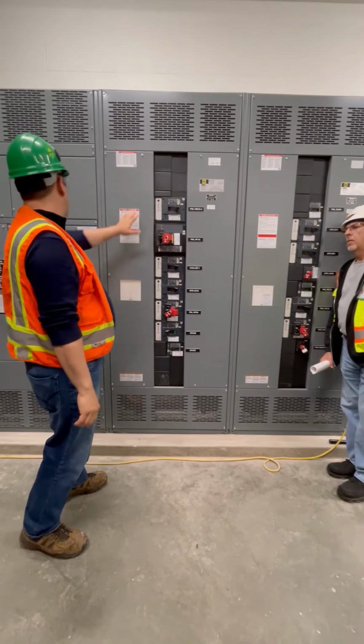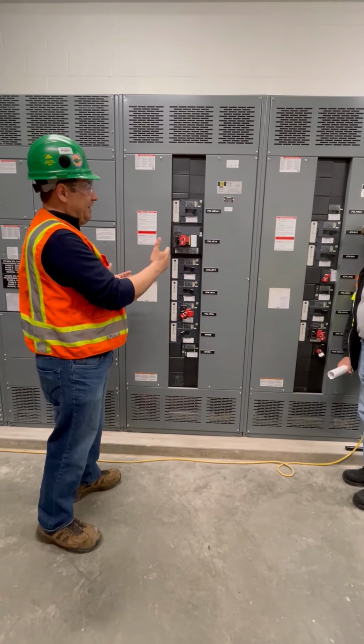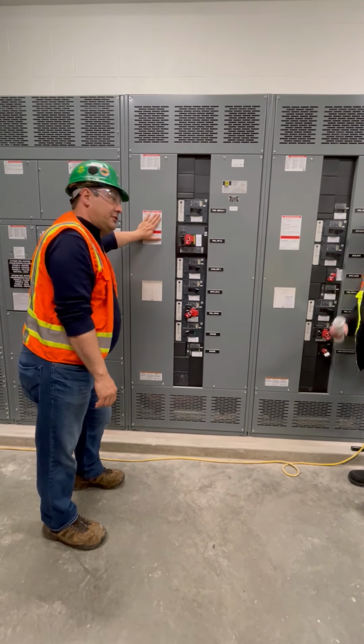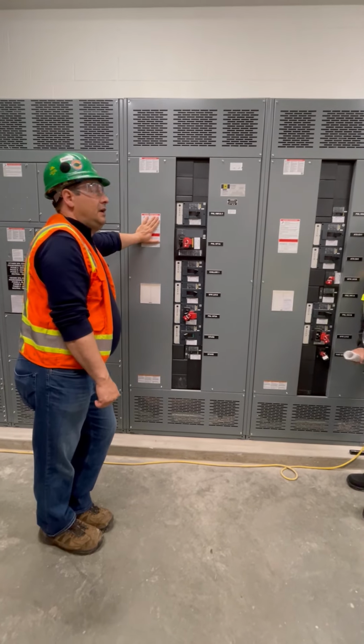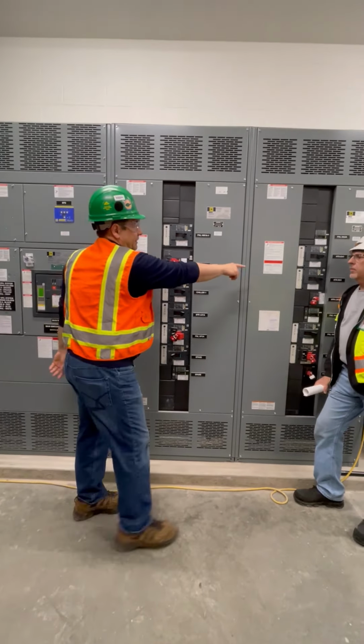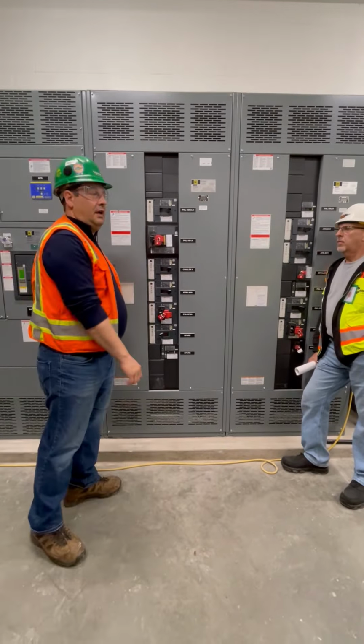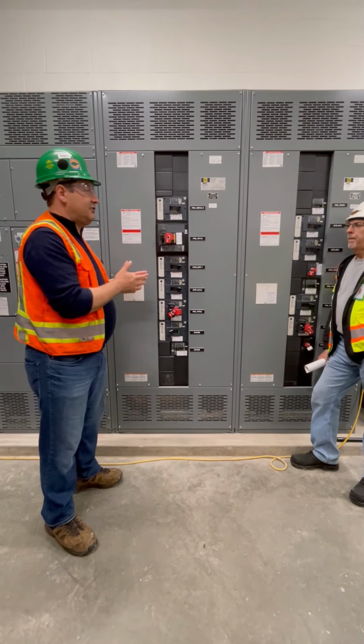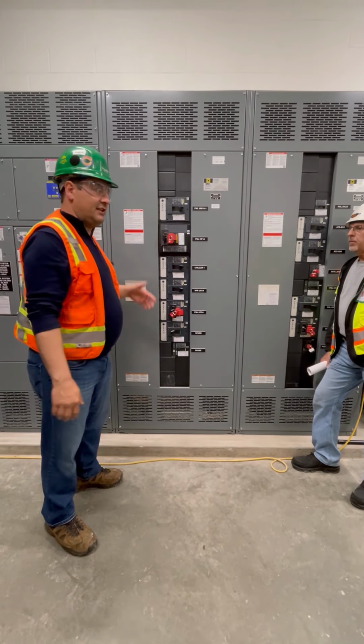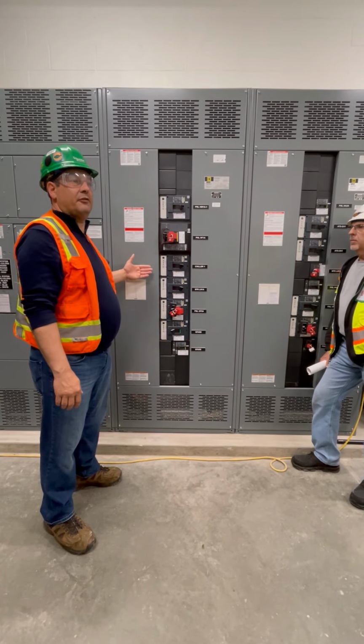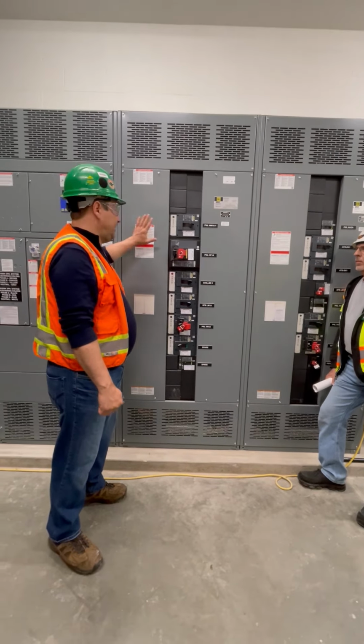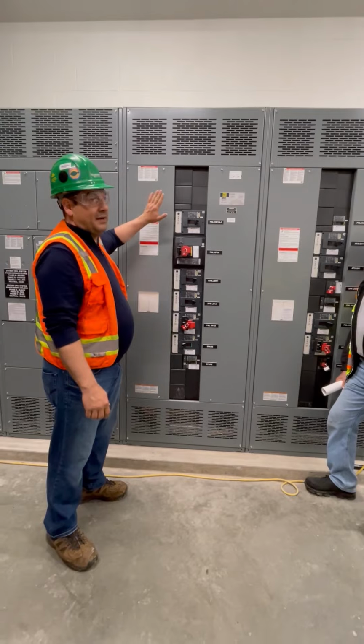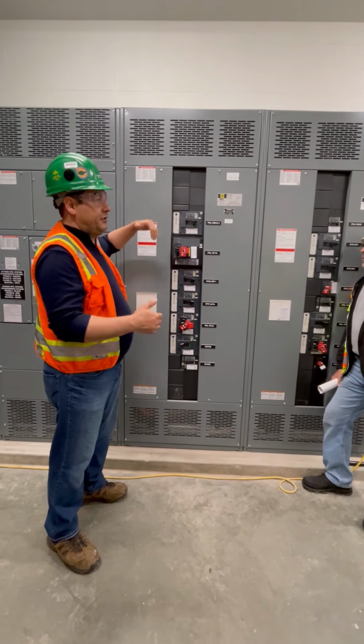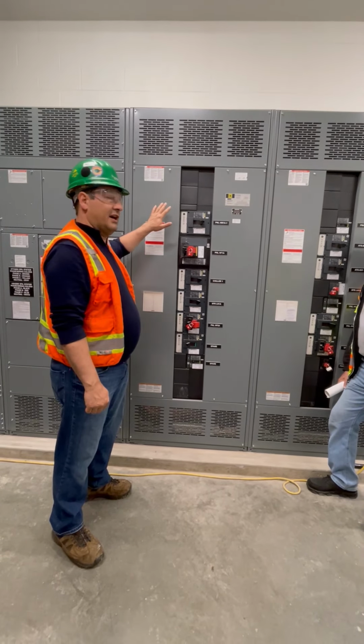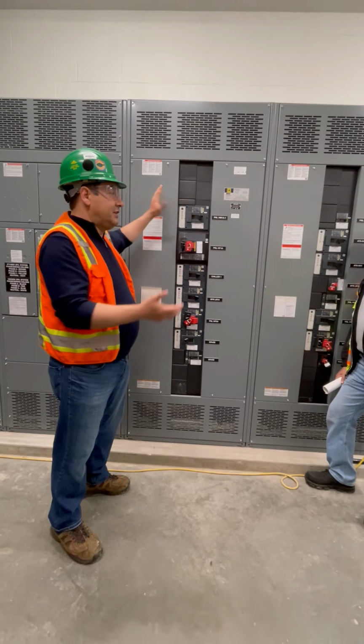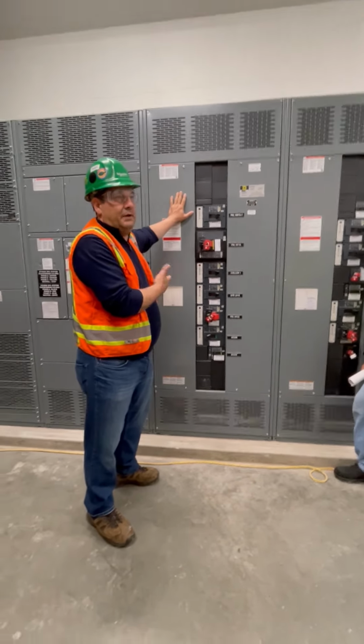Same thing on those. If you're interested, if you have an IR program, especially since this one is prohibited, you can't take covers off. Even if you're suited up, you can't take these covers off in order to do the infrared. So that's why those covers that we have may be very valuable to you, because you don't have to expose yourself or the thermographer to the switchboard, because they cannot do thermography anyway.